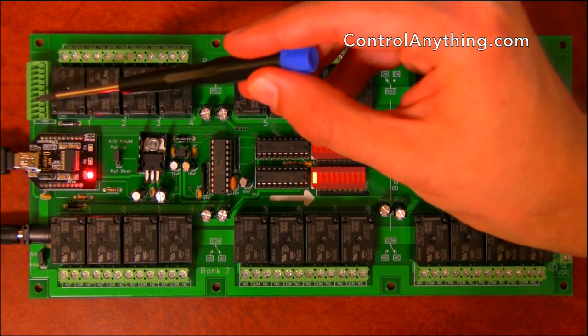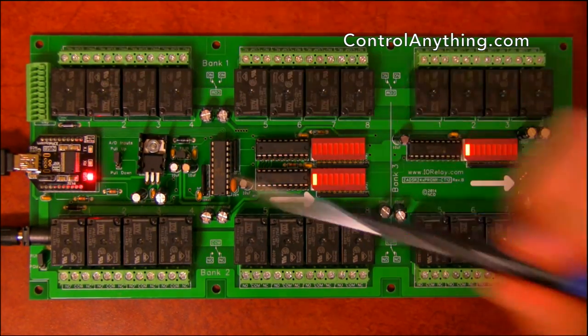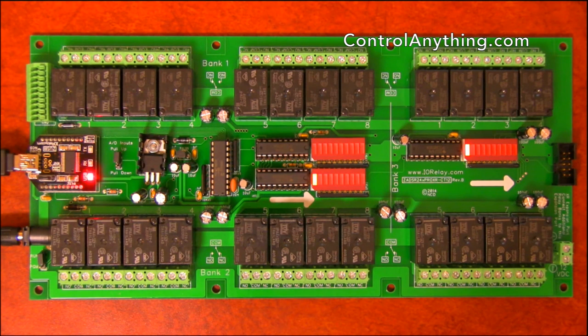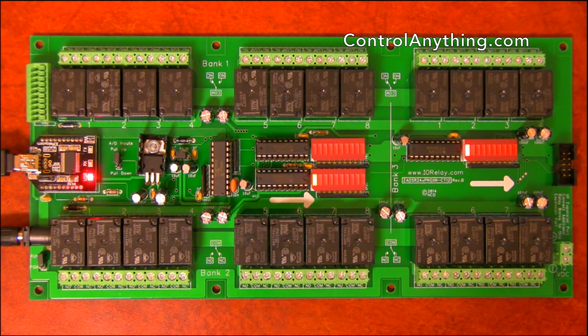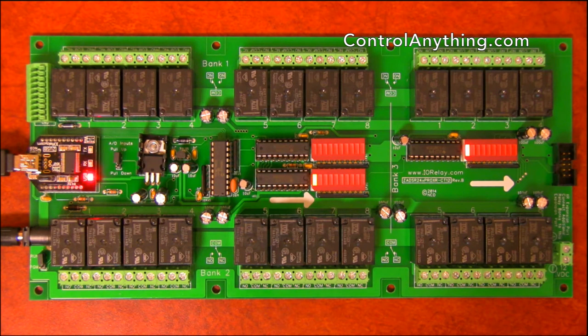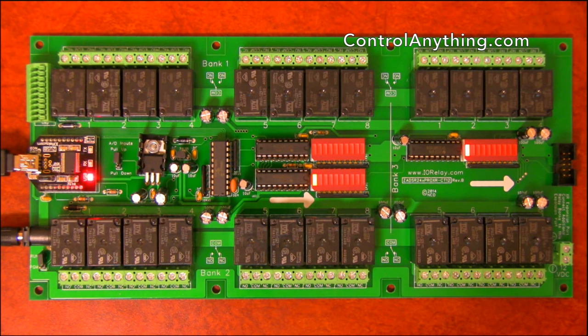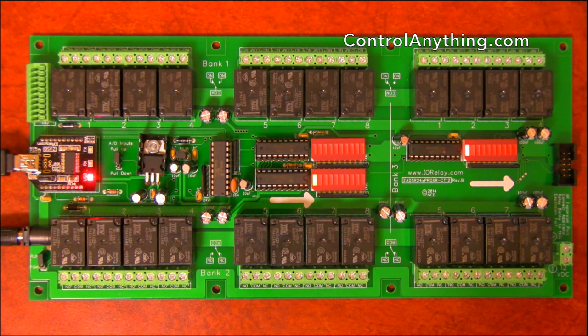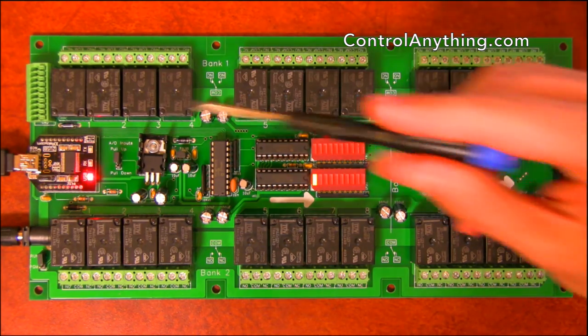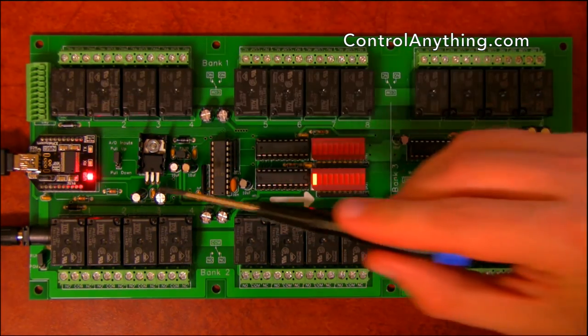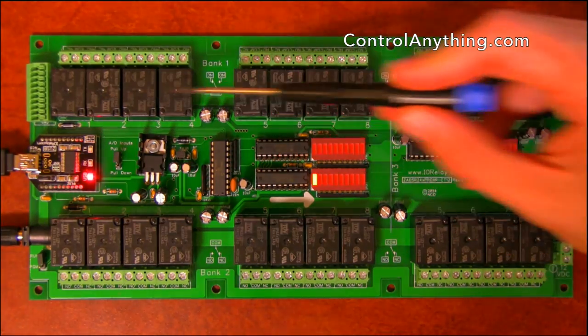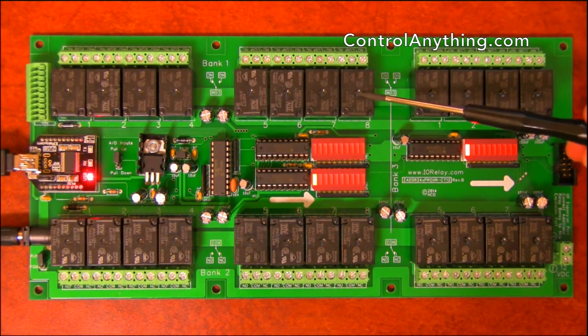Also over here we have eight analog inputs. These inputs can be used to read temperature sensors, humidity sensors, pressure sensors. Anything that outputs a zero to five volt voltage can be read by the analog inputs. There are eight of them. And these analog to digital inputs have a zero to five volt voltage range. Also these analog inputs can be configured to directly control the first eight relays on this controller.